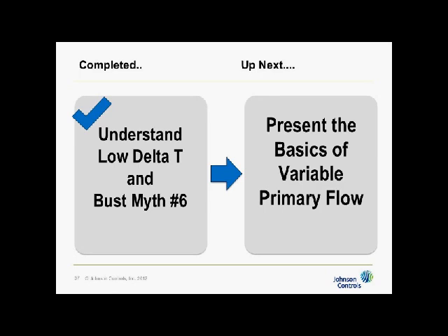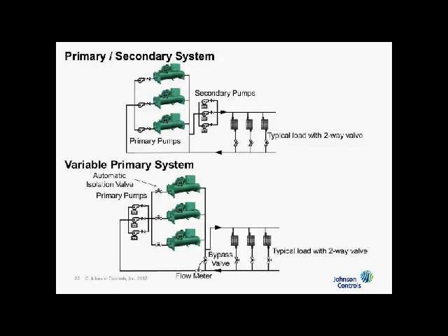Now let's look at variable primary flow. Here's our primary-secondary system up here, just for comparison. Here's our variable primary flow system down here. The difference is that I have down here bigger primary pumps because I'm combining primary and secondaries together into one pump. I have no secondary pumps to place. I don't have any space that I've got to use in the plant room. I don't have to wire them. I don't have to install them. I don't have to buy them. I don't have to rig them. I haven't got any of the costs associated with that. So typically, variable primary flow will cost less to install than primary-secondary.